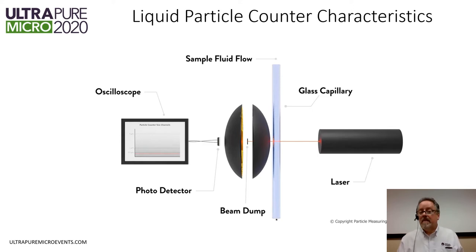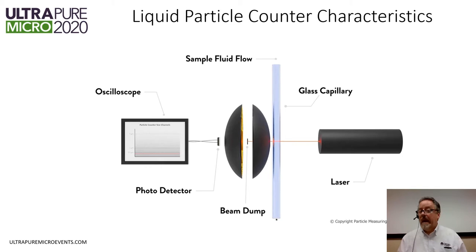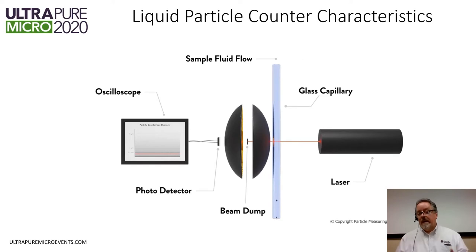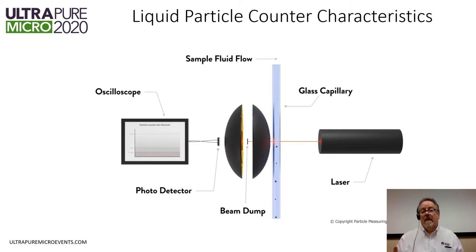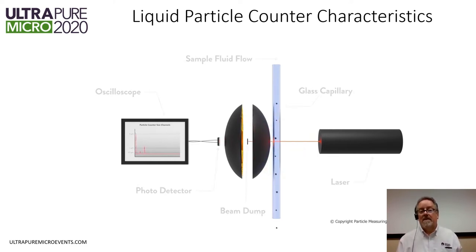This is a typical liquid particle counter. We have a light source, a laser, and a means of focusing the laser down to a flow capillary where the fluid that you want to measure is passing through. You have a means of collecting the scattered light that occurs when the particles pass through the laser beam, and you focus that light down onto a photo detector, which creates an electronic signal that you can measure.